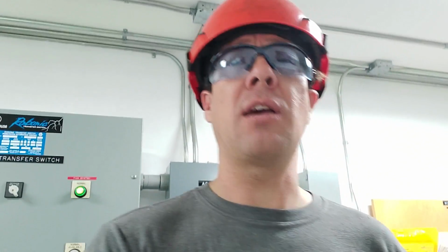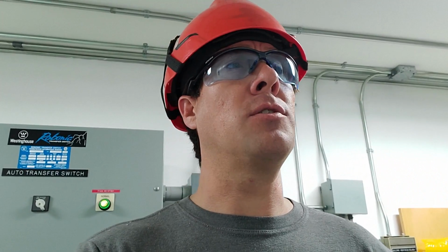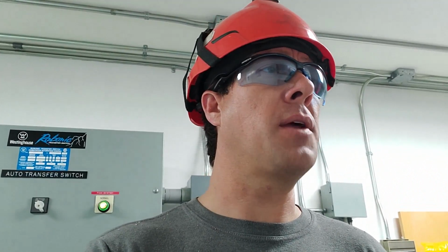If there are ongoing issues, I will actually go to the substation and check the counter. Let's say it is 1111, and the customer said yes, it blinked 3 times in the last week. I'll go back and that counter will read 1114. So again, I can explain to the customer that there's something on the main line, and we'll investigate further and focus our troubleshooting on the main line, to see if there's an insulator that's failing or something.